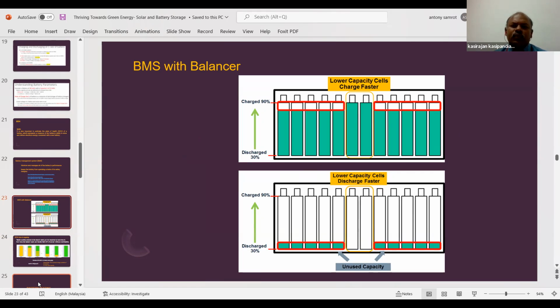They will charge faster compared to normal healthy batteries. So what is the disadvantage? If the lower capacity cells charge faster, it will indicate to the BMS that it's fully charged, but other batteries are still at 90% only. This affects performance, since the other batteries are only 90% but these lower capacity cells are at 100%, so it immediately stops charging. That is one disadvantage.